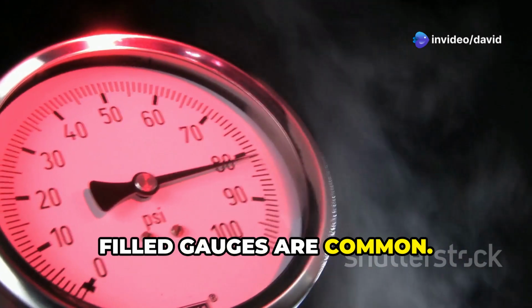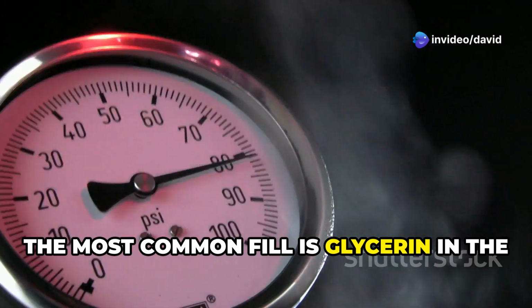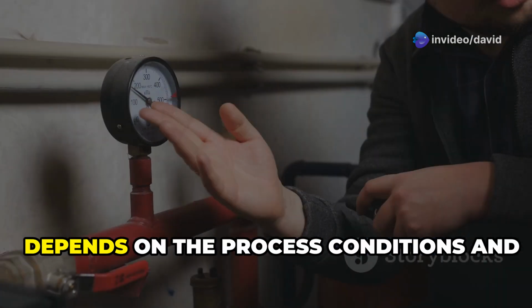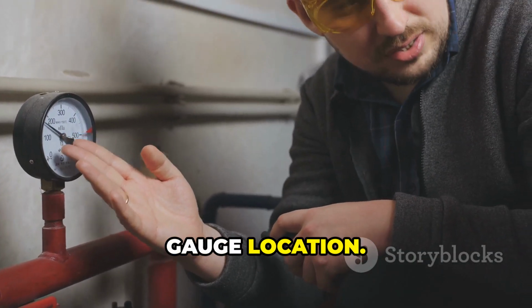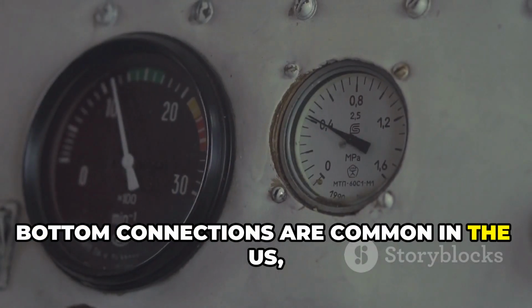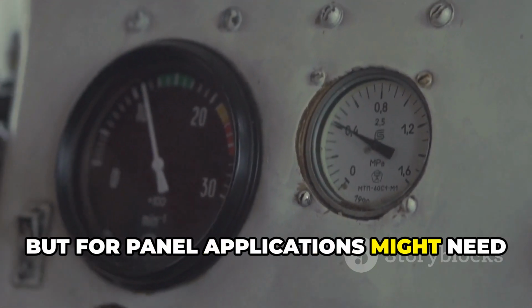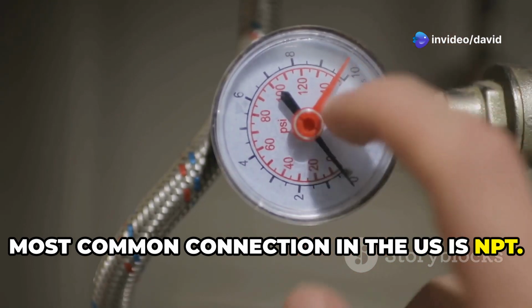Filled gauges are common. The most common fill is glycerin in the offshore world. Depends on the process conditions and gauge location. Bottom connections are common in the US, but for panel applications might need bottom back connections. Most common connection in the US is NPT.